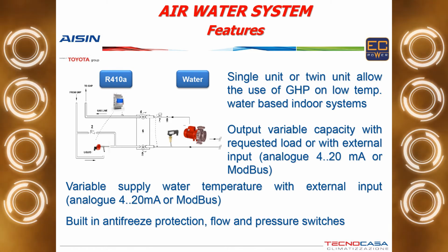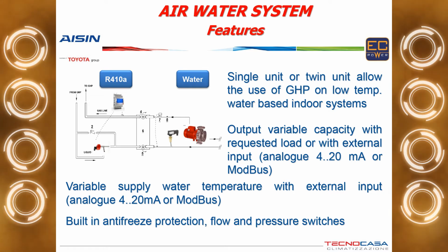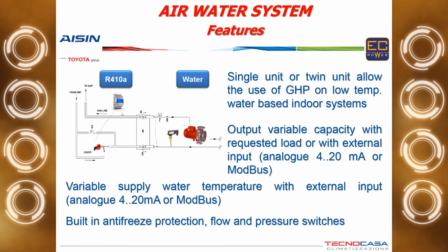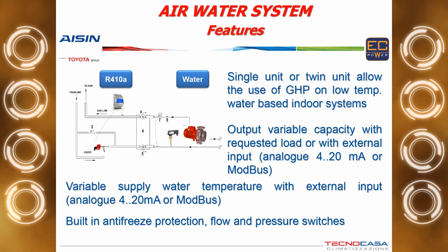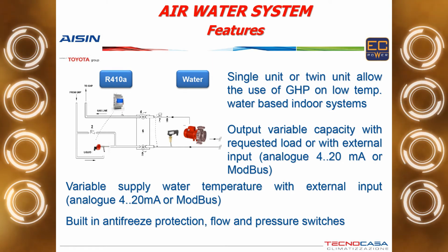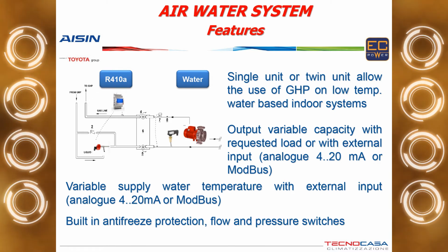So actually we can change the supply temperature, and using an external temperature probe, we can also make something like a water changing temperature system. So the water temperature will increase when the outside temperature is dropping. Working with lower supply temperatures, of course, increases the GUE of the gas-driven heat pump. There is a built-in antifreeze protection because the unit can be installed outside as well. So we provided the system with the software to avoid ice forming in the unit, and to reduce the amount of glycol that you have to put in the system to protect it from freezing.